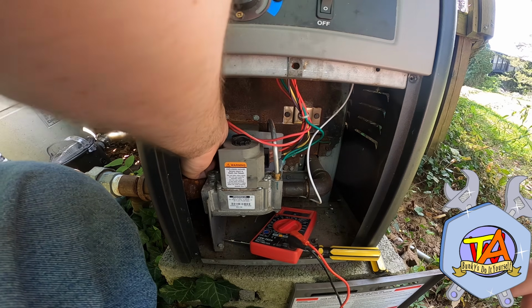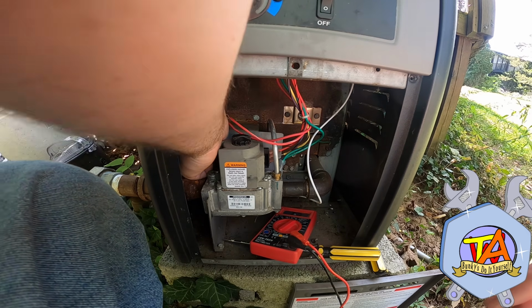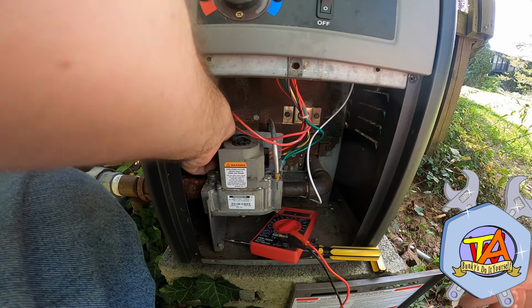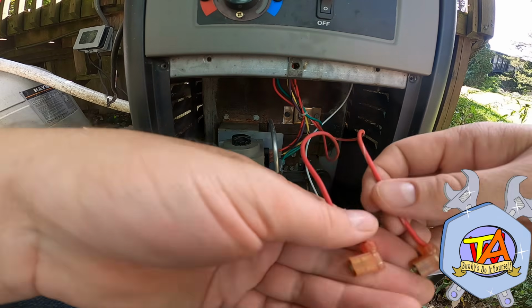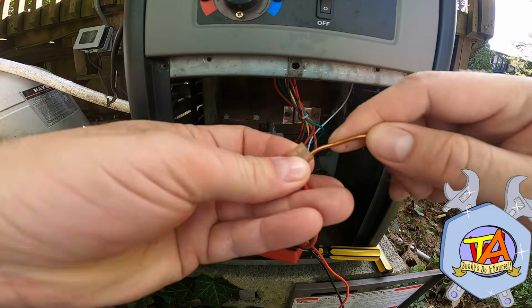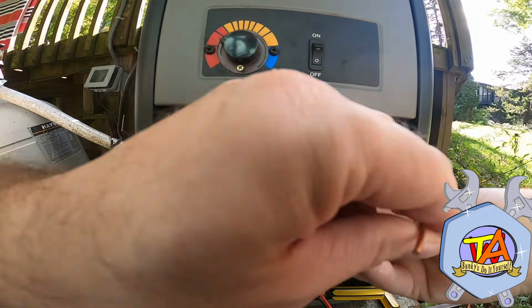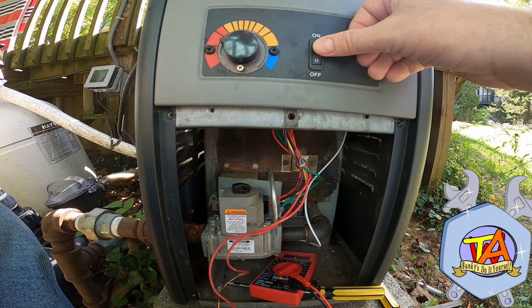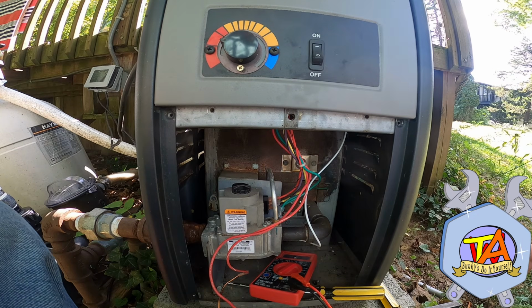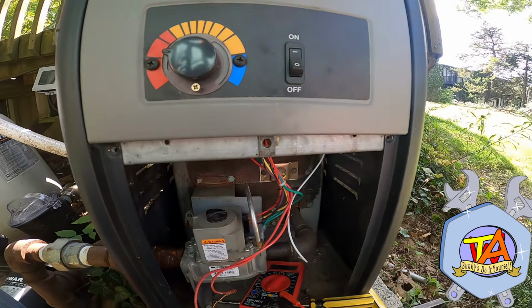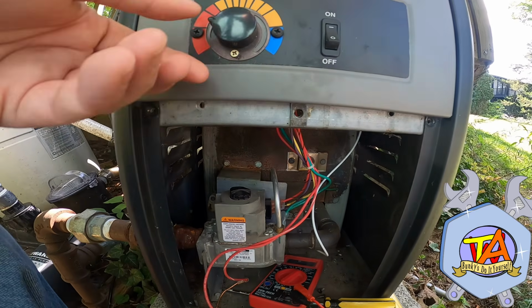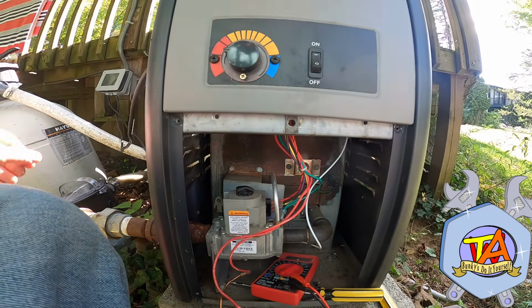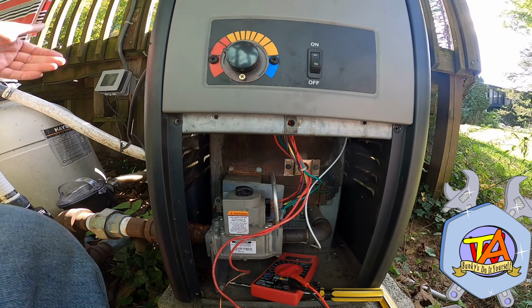I'm going to go ahead and detach these wires from the rollout switch and bypass it with a wire. I'd much rather you do this with an insulated wire than what I'm doing. Now I can flip on the on switch and see if the heater kicks in. That clicking sound is the igniter. Now I don't have the gas on, so it's not going to start.